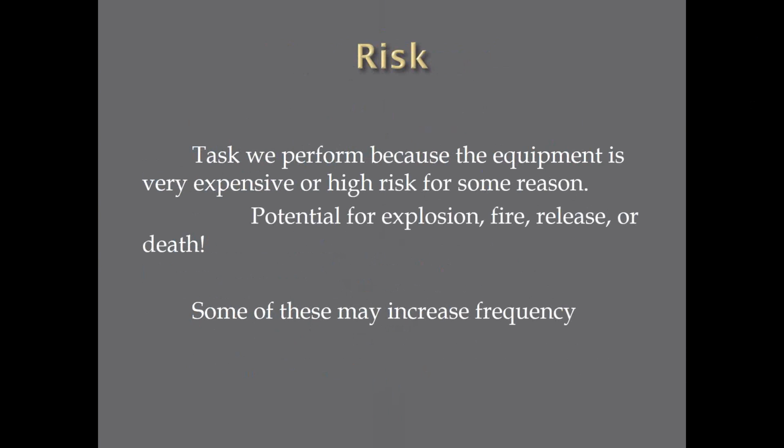I was just recently at a plant in Canada where they had a big electrical fire in one of their switchgear boxes. The fire caused a lot of damage, destroyed the whole switchgear. Luckily, they had some stuff that was still in stock from when they built the plant. Otherwise, they'd have been down for weeks. They were only down a couple of days rebuilding this.